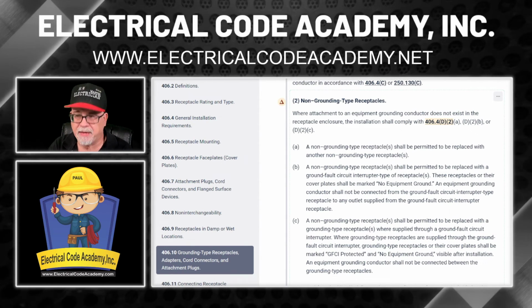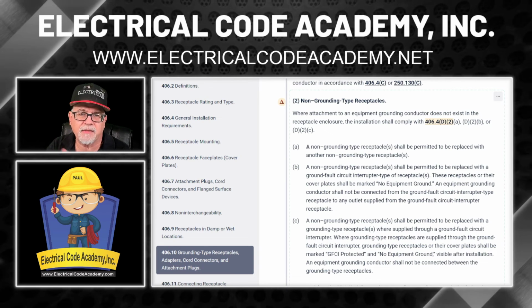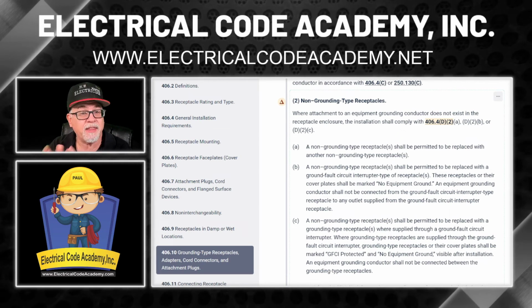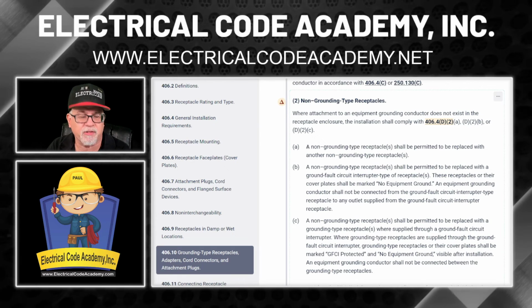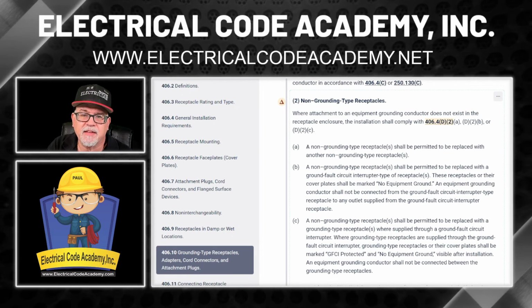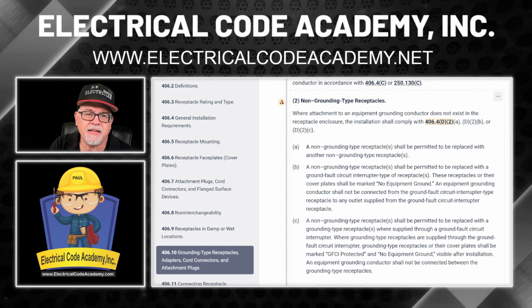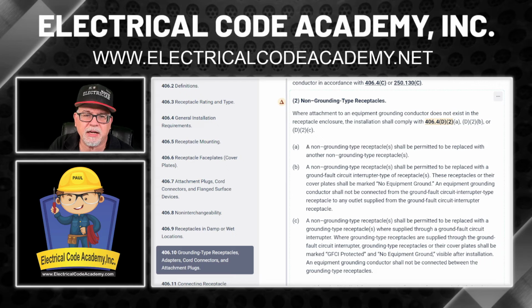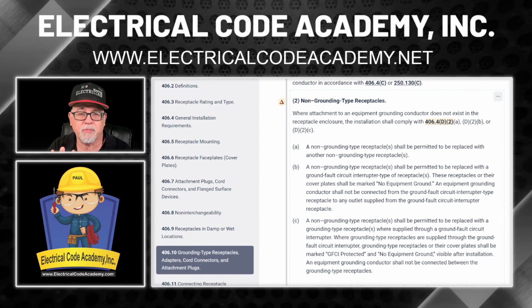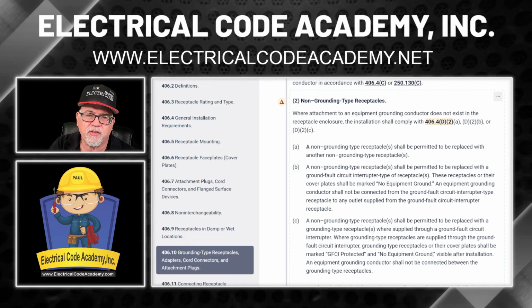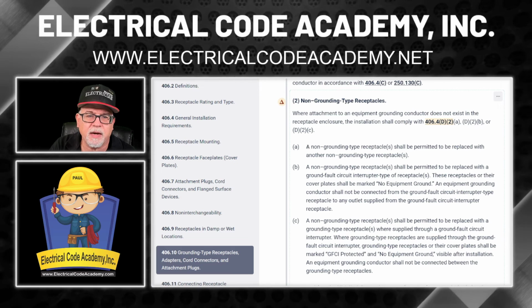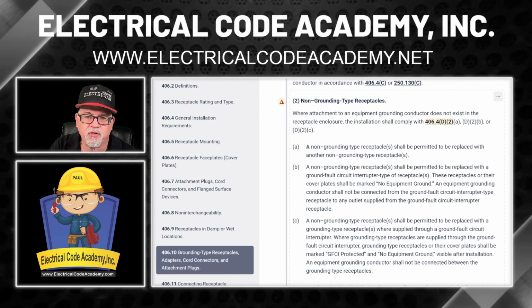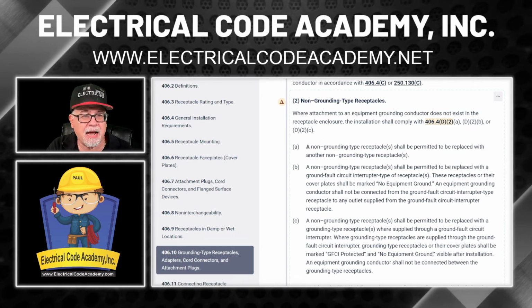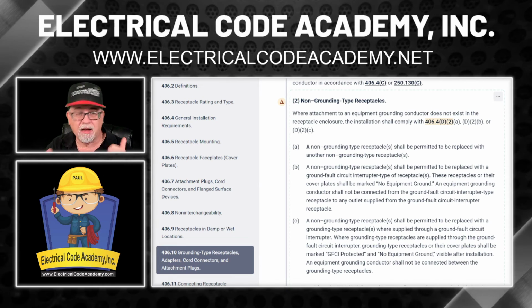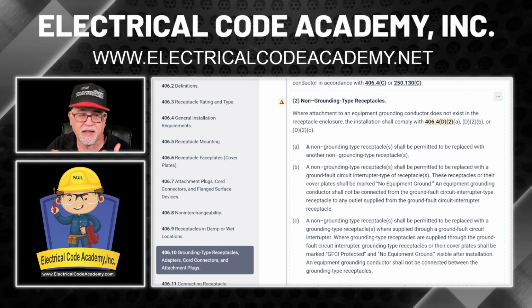Now, B is a little different. This is one that he did based on his video. It says, non-grounded type receptacles shall be permitted to be replaced with a ground fault circuit interrupter type of receptacle. That's what he did. Okay. It says these receptacles or their cover plates shall be marked no equipment ground. And that's what he did. He put the little label that comes with the GFCI. He's good. It then goes on to say an equipment grounding conductor shall not be connected from the ground fault circuit interrupter type receptacle to any outlet supplied from the ground fault circuit interrupter. So if you're extending from that one onto another one and you're thinking, oh, well, now I'm going to use the right type of wire and cable that does have an equipment ground.